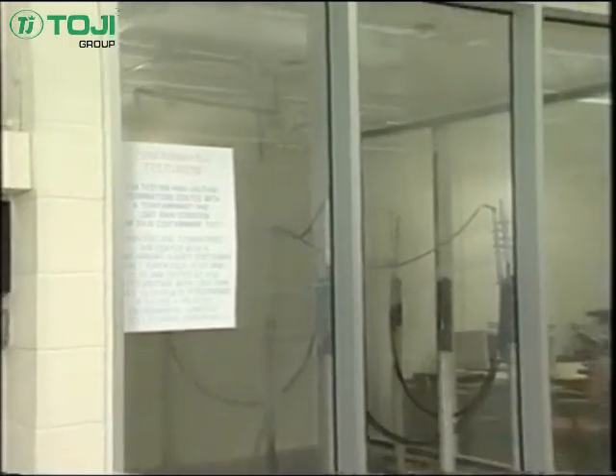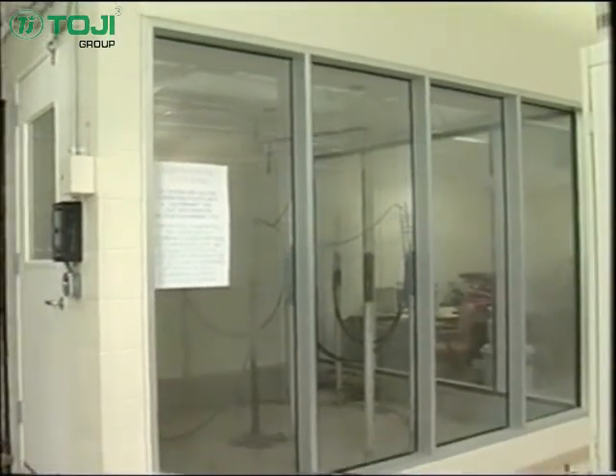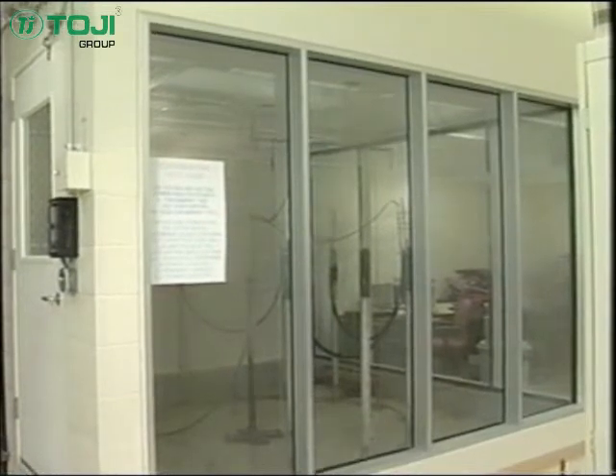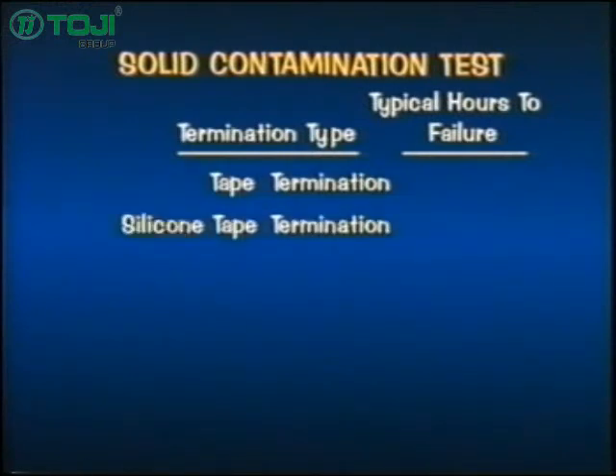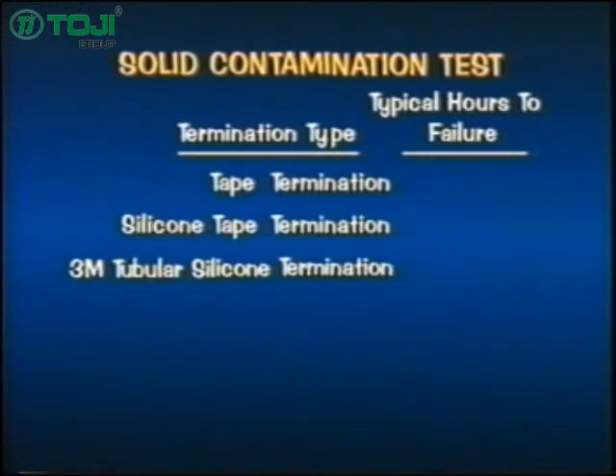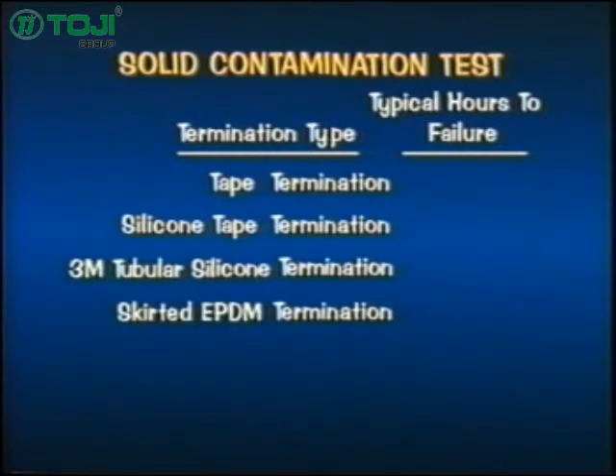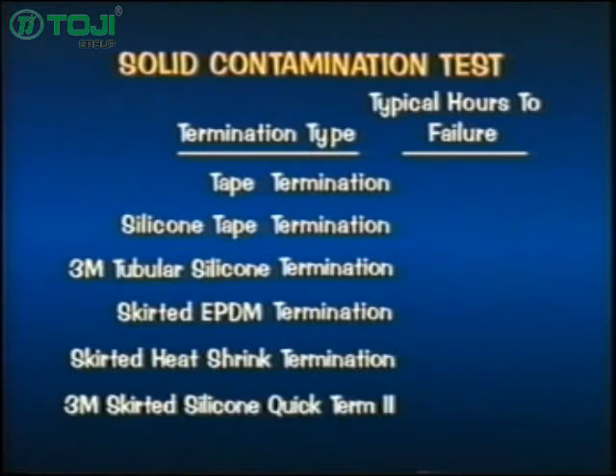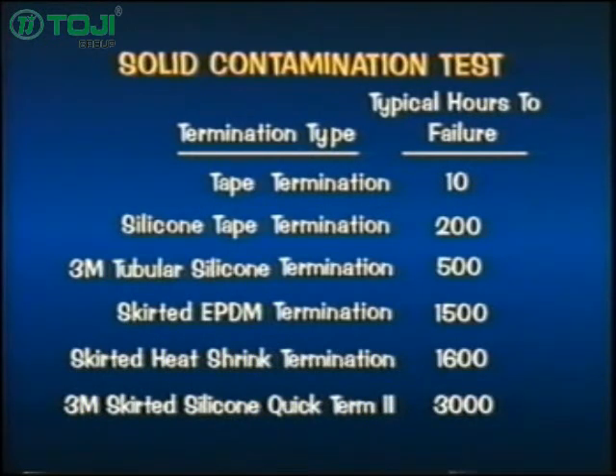3M routinely runs tests that simulate an industrial high-humidity seacoast environment. Terminations are exposed to an ASTM contaminant mixture of water, flint, clay, salt, and paper filter pulp. A voltage of 150% rated voltage is applied to the cable. The tests have included non-silicone tape, silicone tape, 3M tubular silicone quick terms, skirted EPDM terminations, skirted heat shrink terminations, and 3M Cold Shrink skirted silicone Quick Term 2. As you can see, the difference in the hours to failure with the 3M skirted silicone Quick Term 2 termination, with its superior hydrophobic properties, is very significant.